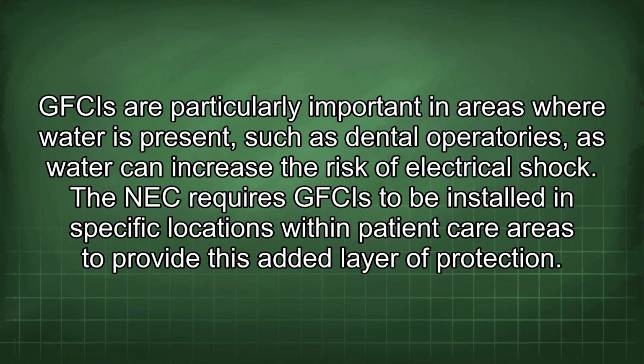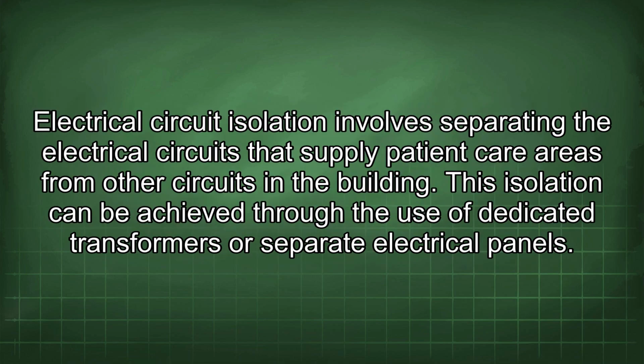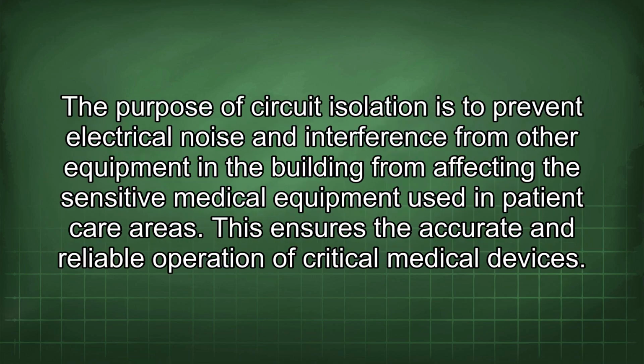The NEC requires GFCIs to be installed in specific locations within patient care areas to provide this added layer of protection. Electrical circuit isolation involves separating the electrical circuits that supply patient care areas from other circuits in the building. This isolation can be achieved through the use of dedicated transformers or separate electrical panels. The purpose of circuit isolation is to prevent electrical noise and interference from other equipment in the building from affecting the sensitive medical equipment used in patient care areas. This ensures the accurate and reliable operation of critical medical devices.